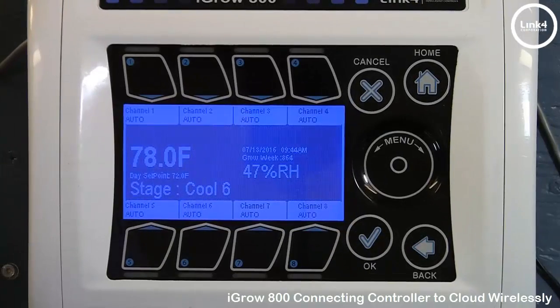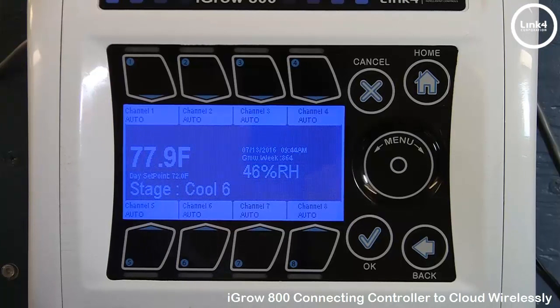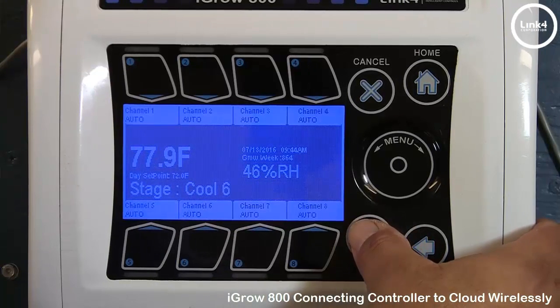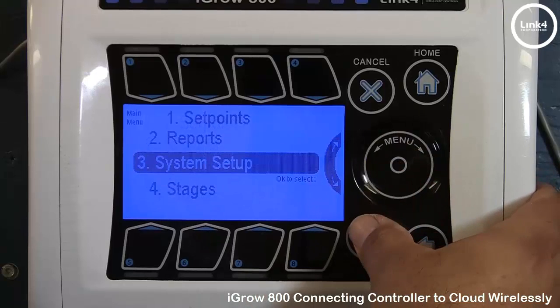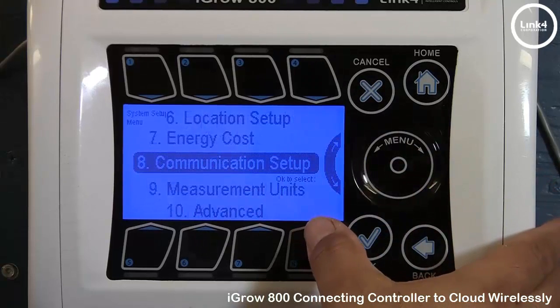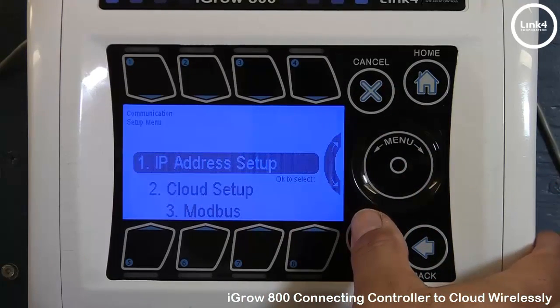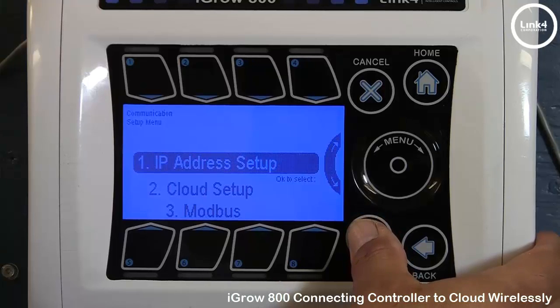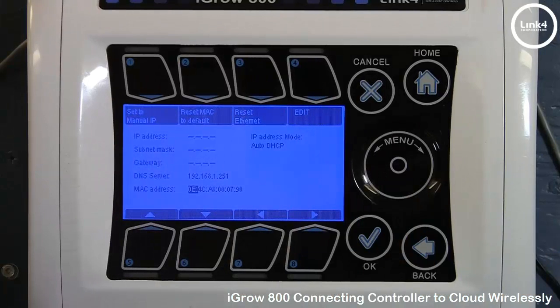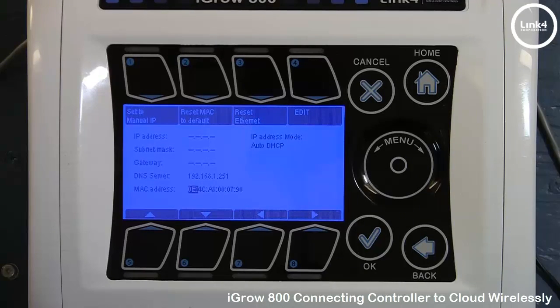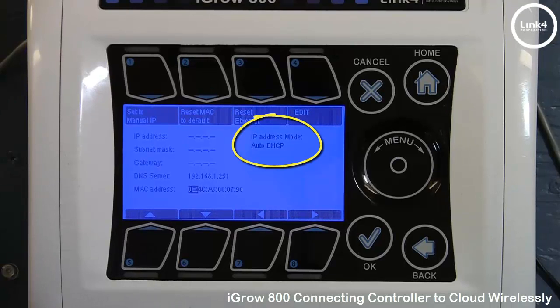From the iGrow 800 controller, we want to check something out first. We'll hit OK, go to System Setup, then number 8, Communication Setup, and then IP Address Setup. As you can see in the IP Address Setup screen, all of our IP address information is not populated. You want to make sure that the IP Address mode is, in fact, in Auto DHCP.